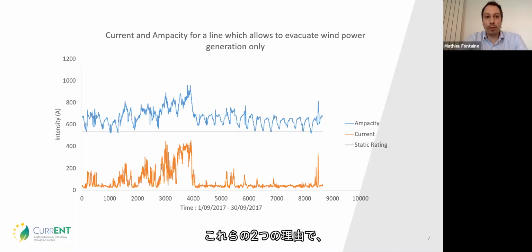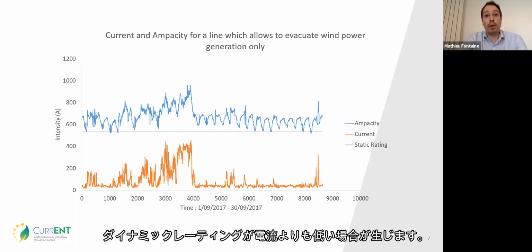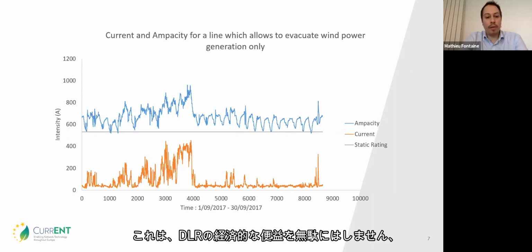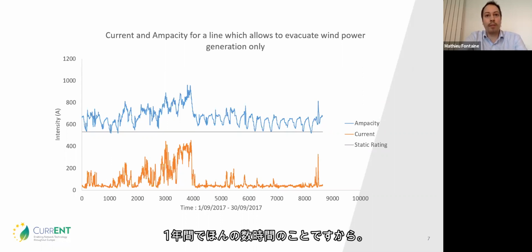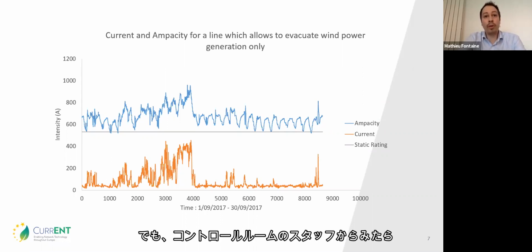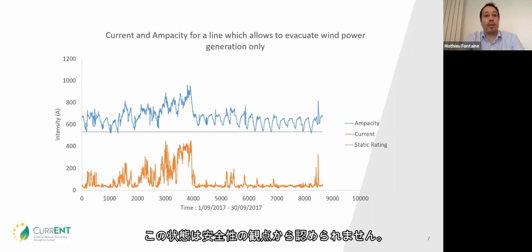These two reasons may occasionally cause a dynamic line rating lower than the line current. Even if this does not challenge the economic benefits of DLR, since it's only a few hours per year, for operators in the control room it seems unacceptable for security reasons.